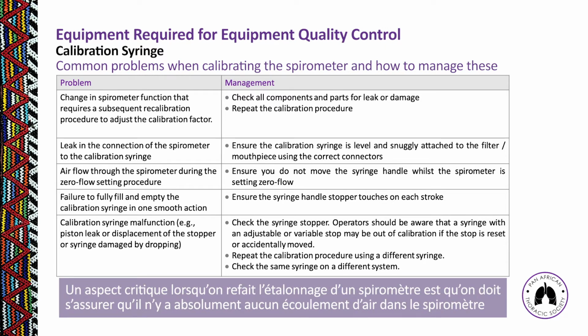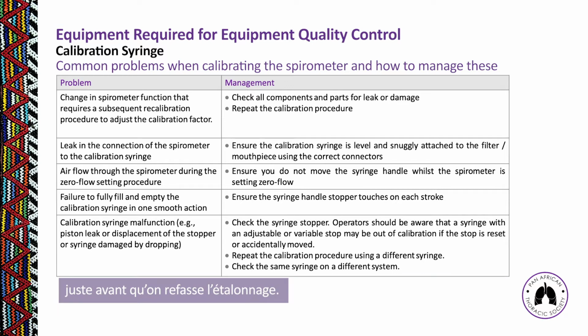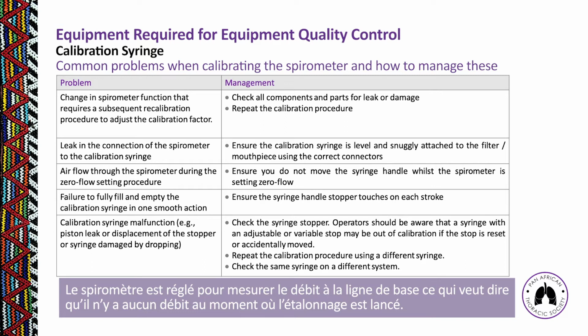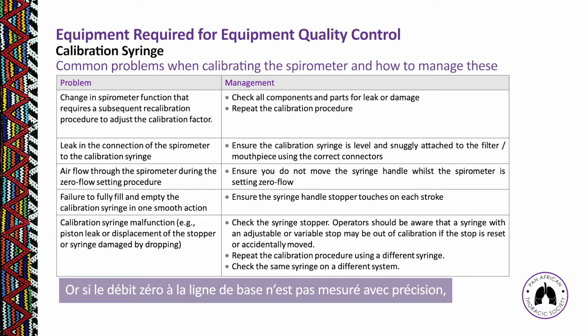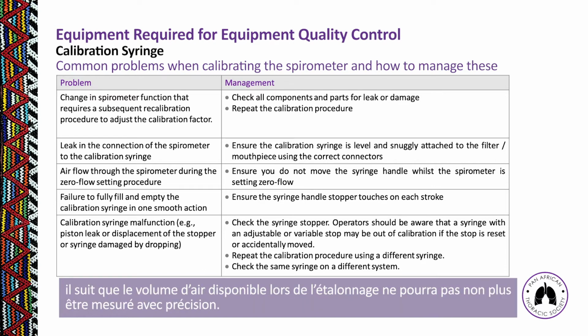A very important part of calibration is making sure that there is no air flowing through the spirometer immediately before the calibration check takes place. So the spirometer is set up to measure baseline airflow. What that means is that there's no flow of air at the time that you start the calibration. The reason for this is that if the baseline airflow is not measured correctly, then the amount of air that you are looking at when you are calibrating the machine will also not be measured correctly.